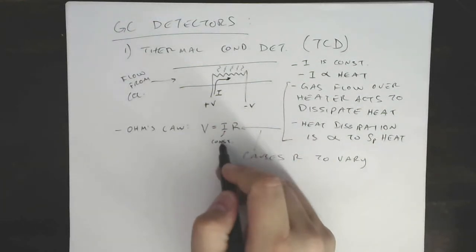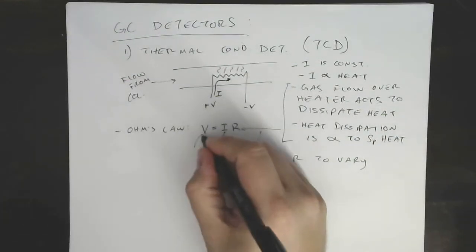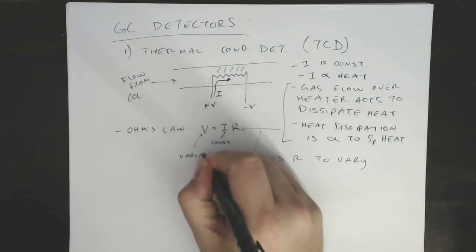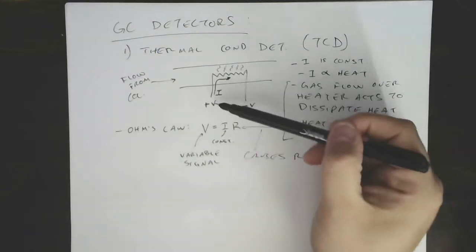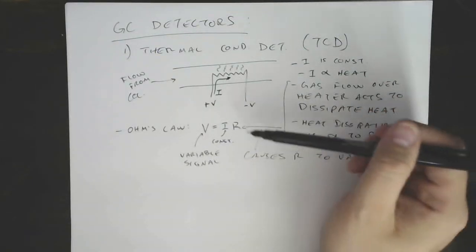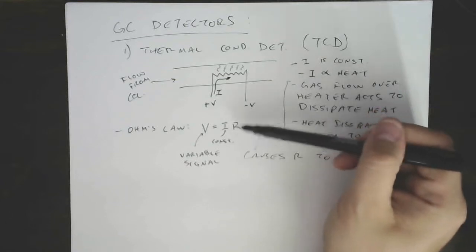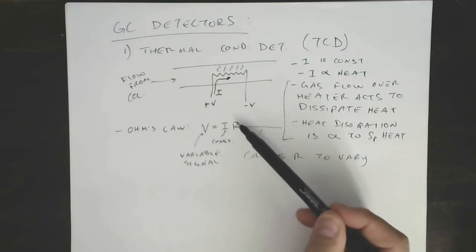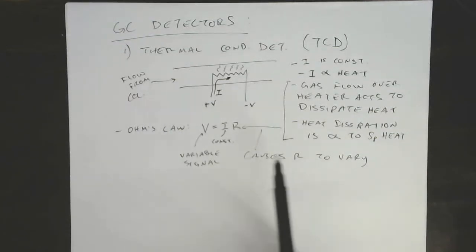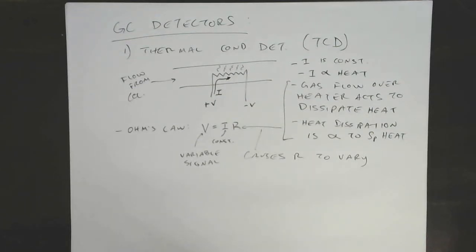If you have a constant current in a system where resistance is changing, you get a variable voltage signal. If you measure what voltage it takes to drive that constant current in a dynamic system where resistance is changing, the voltage you need will change. And because this changes as a function of the specific heat of the gas, it changes as the gas composition changes — which changes when a peak is present or not, ideally proportional to how much extra material is in that peak.